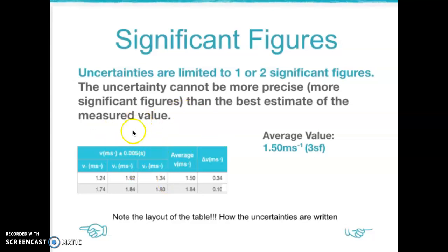You must make sure that you have a section which expresses the uncertainty, the instrument uncertainty. And if you're taking repeat readings, you can express it as a split cell here, like that, over the 3 different readings.